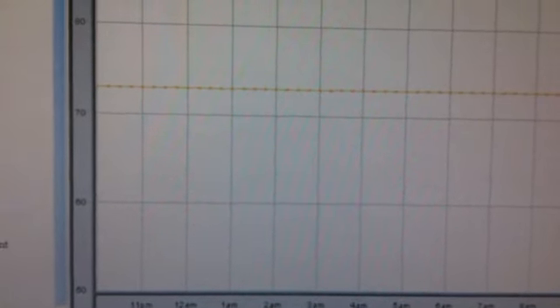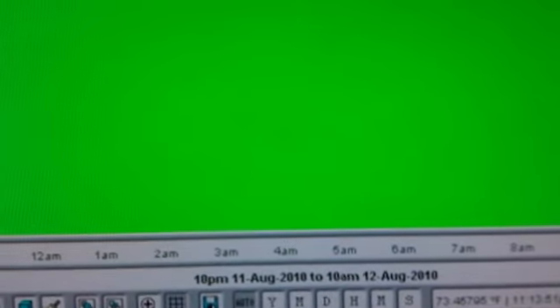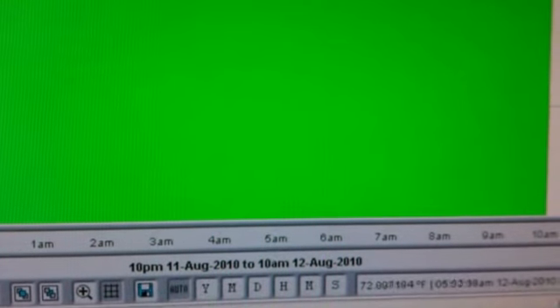Checking how accurately this space temperature is tracking. Take the space temp out. That yellow line is what we want it to be, which is 73 degrees. And if I put space temp back in there, that's tracking within a couple tenths. Let's see, there's the peak, 73.27. Where's one of the valleys? 72.8. So within a half a degree swing, I have some of these tracking the rooms. That's the air handlers that have the modulating water valves.